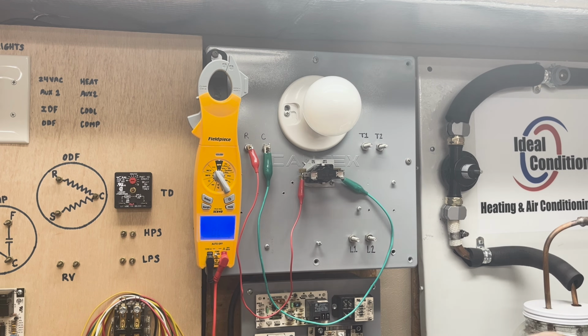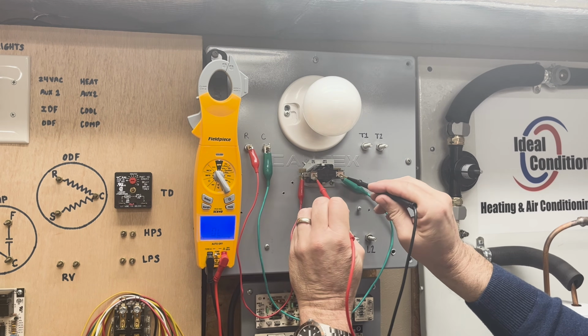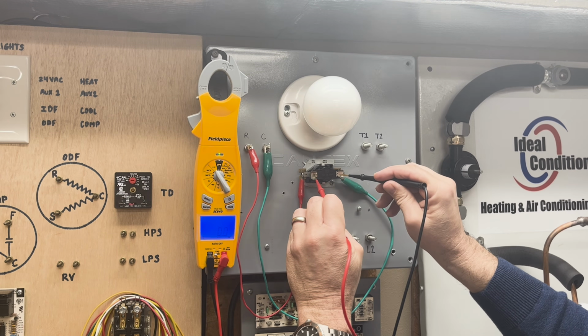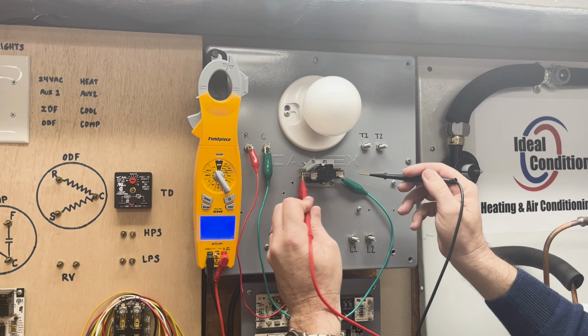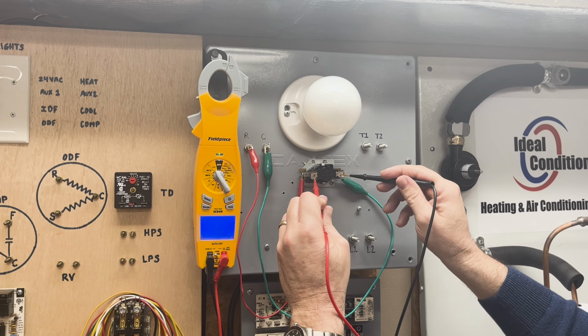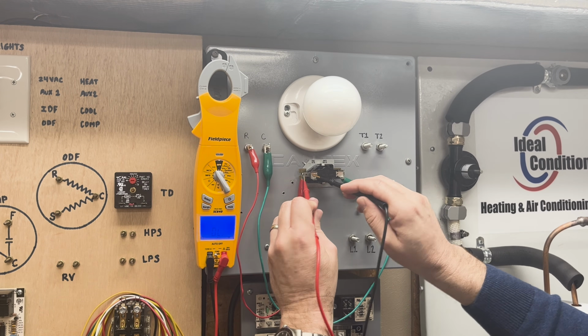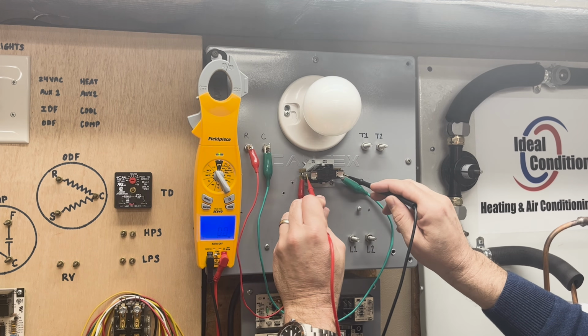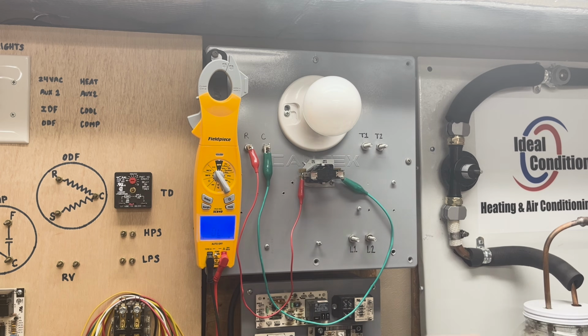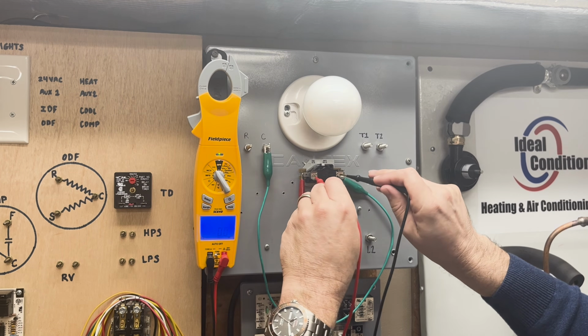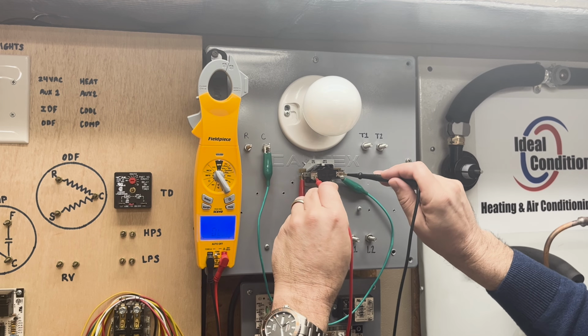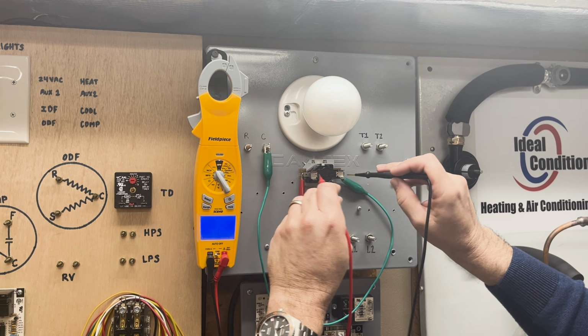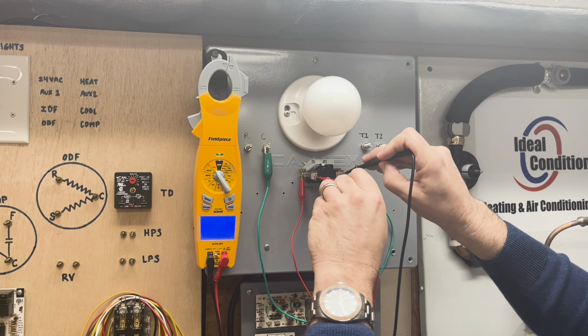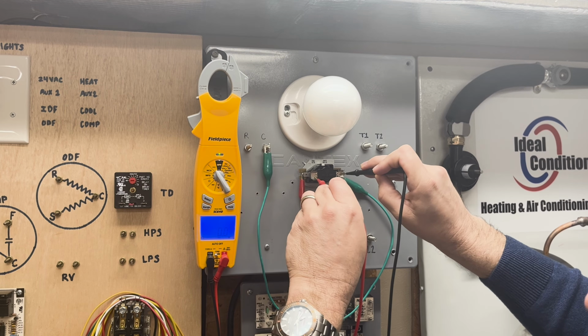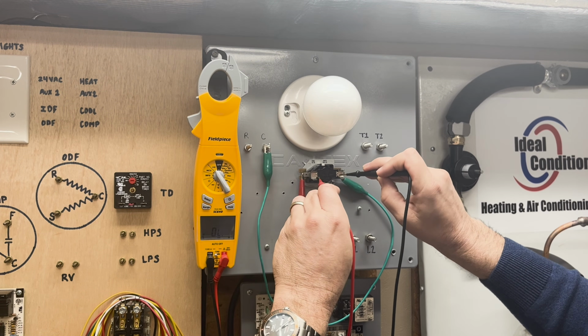There we go. We'll probably go to ringtone here because it's only 7 seconds. Here, see, now we have a relay that's good. And now both of these should ring out. See, they're both ringing out. Now, two different poles, so you don't have a ringtone on the same side. It makes across the relay. It makes across the relay. And so now I'm going to disconnect 24 volts. Still closed. Still closed. Okay. Boy, 30 seconds can be a long time when you're waiting on it.